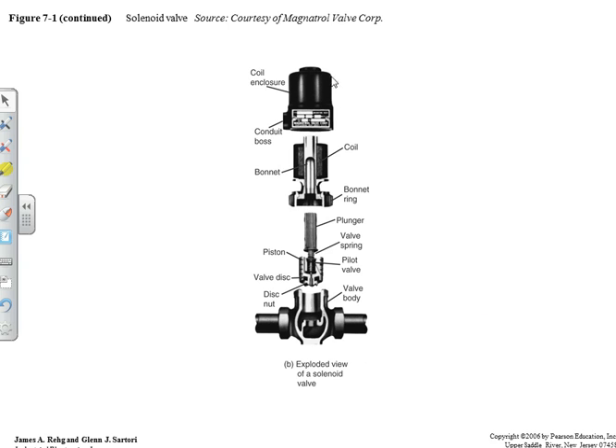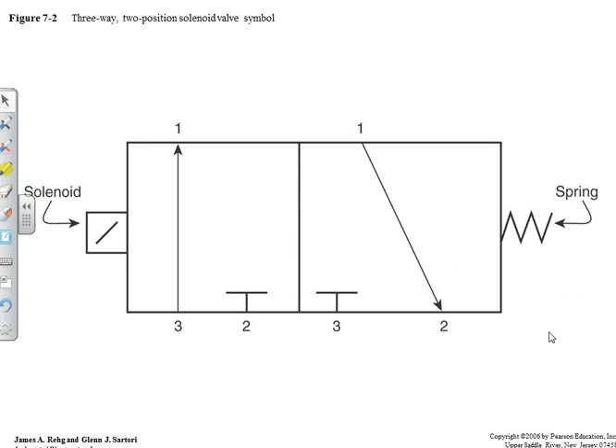So I see that I have some coil, I have something I'm pulling up and down, and it's hooked onto a pilot valve and a piston that sits in the enclosure that goes up and down. I have some valve disc that the plunger hooks onto. Depending on what pressure I am at will depend on whether my liquid has to be on top of the valve or underneath the valve. So at higher pressures, we would expect the pressure to be on top of the valve so I can't open it. If I was underneath the valve with high pressure, I could actually push it open. That wouldn't be good. This is a three-way solenoid valve.